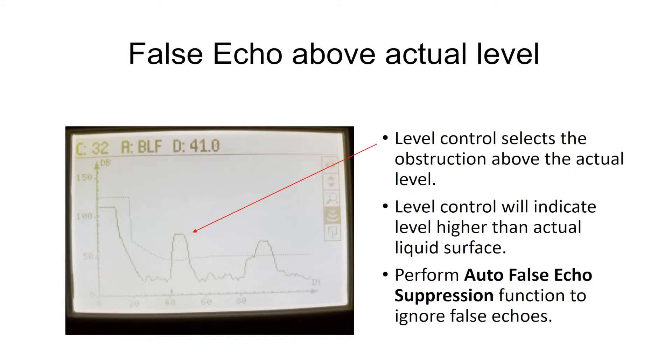For example, if we put a level sensor right above a beam or right above a pipe, we can't see through it. It's for applications where we're getting partial echoes off of devices kind of off to the side. So we can try doing it, but in some cases, we may actually have to move the sensor away from an obstruction.